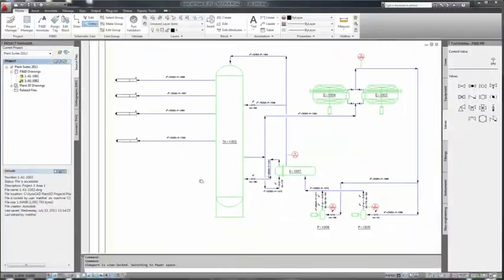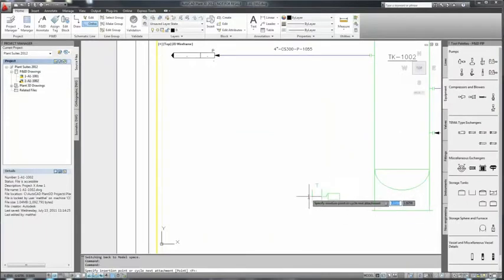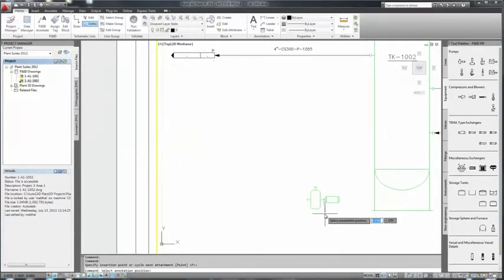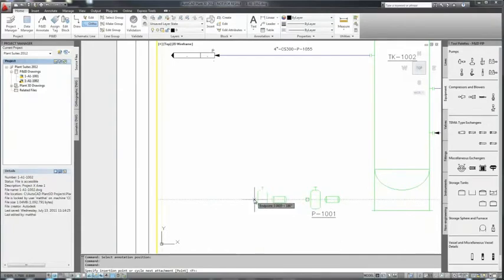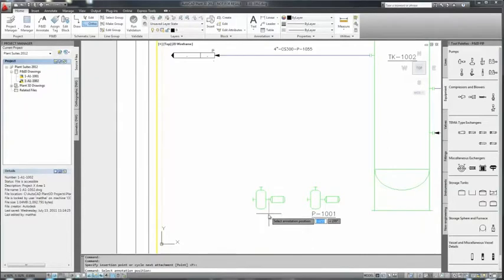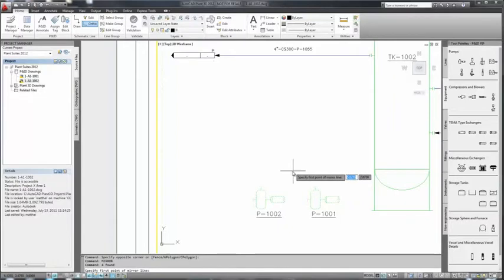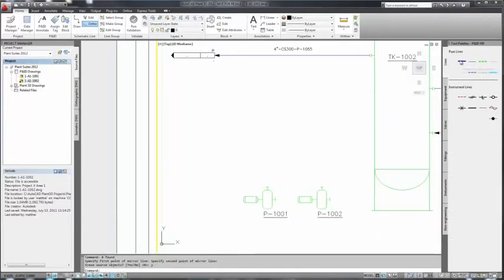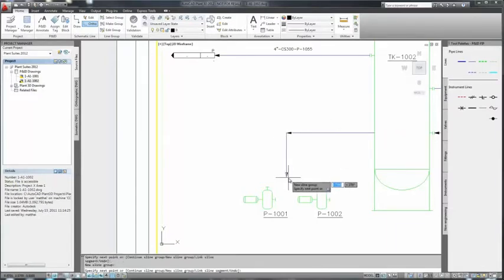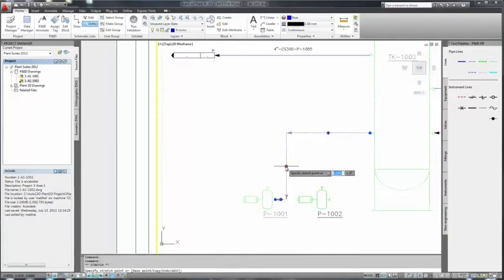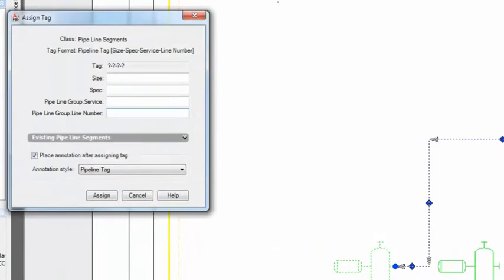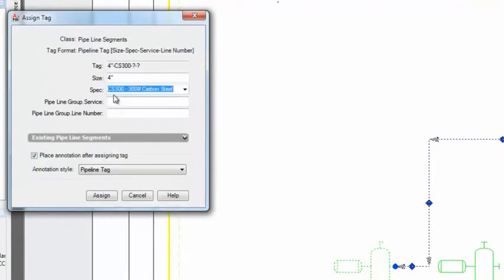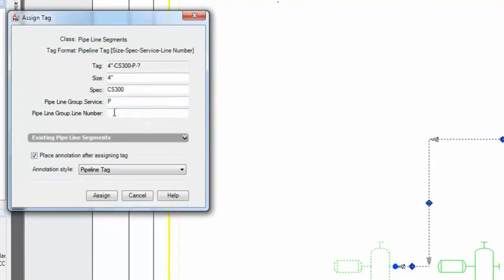So let's take a look at the P&ID. Let's start off by placing some equipment, in this case a pump. And we're just using standard AutoCAD commands here, which will allow us to place it. Then we'll assign a tag. In this case, we'll place a secondary pump. And again, the tag. And now we'll go ahead and place some lines after we've mirrored the pumps. Now, as we place our line, notice that it automatically connects to the input. The drag maintains our orthogonality. And we can assign tags as we go along. And the tags have specific attributes such as size, spec, service, and of course, the number.